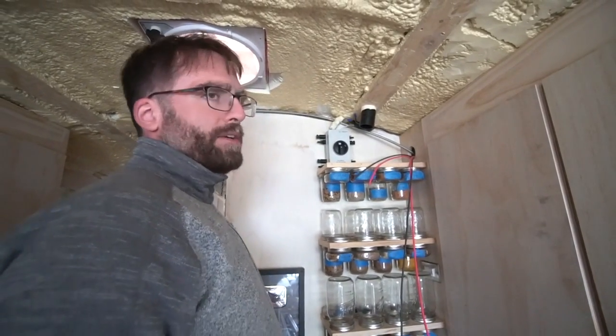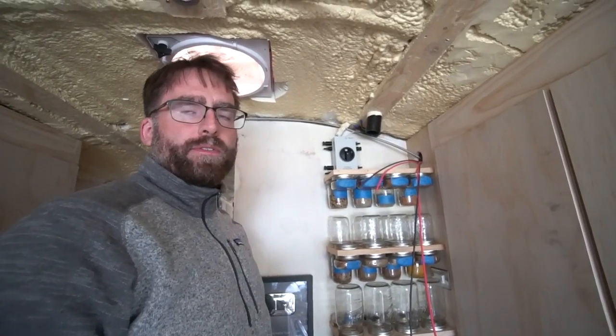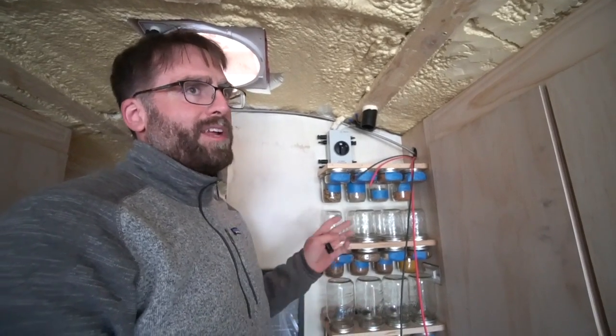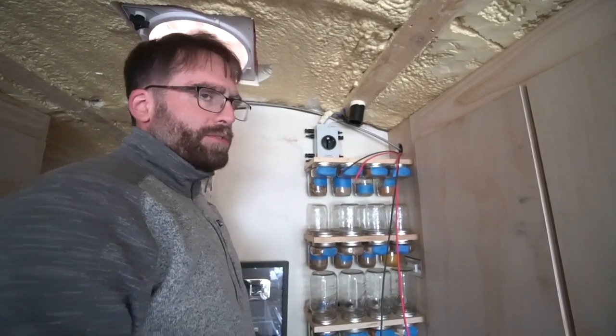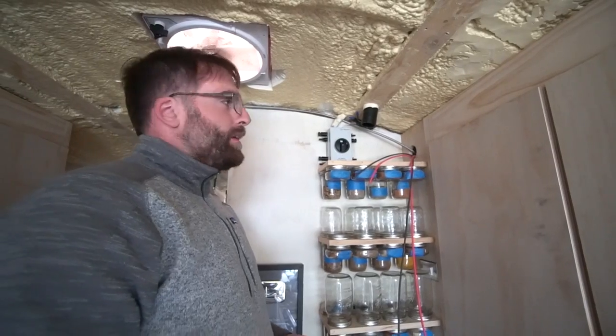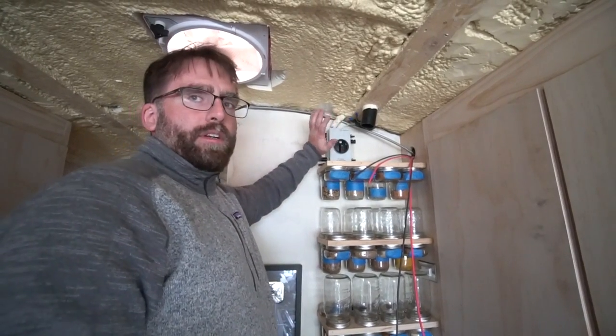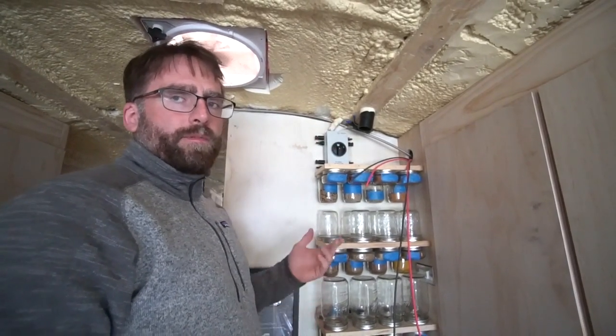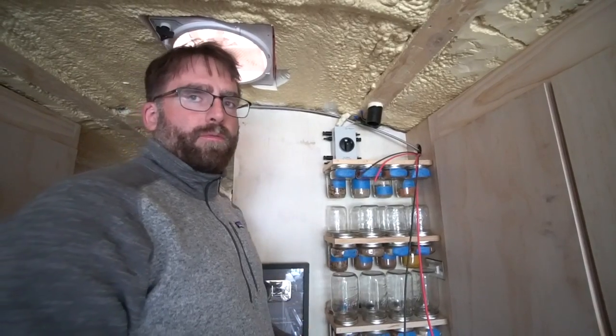You can't just use breakers and stuff when you go above about 100 volts, or actually above about 48 volts. You get all sorts of surprises and stuff. You must use photovoltaic rated equipment to switch it off and on, or DC rated equipment at the correct voltage.